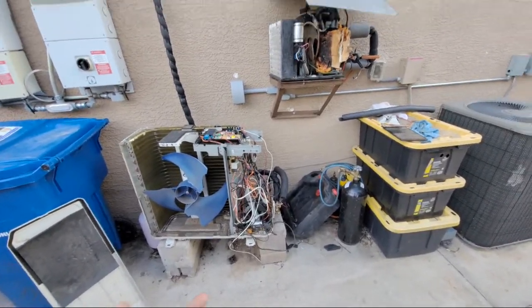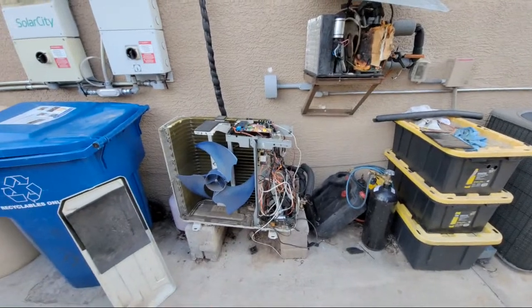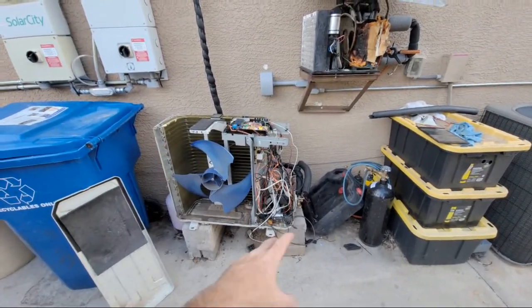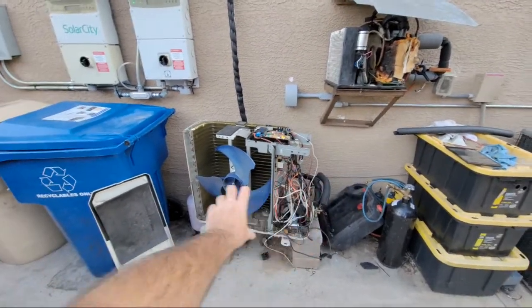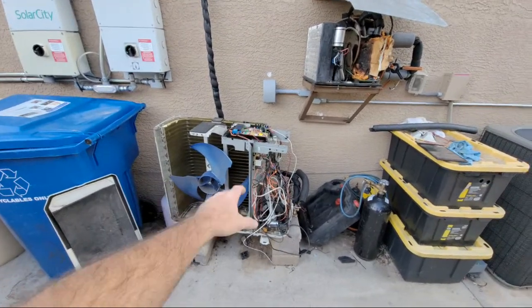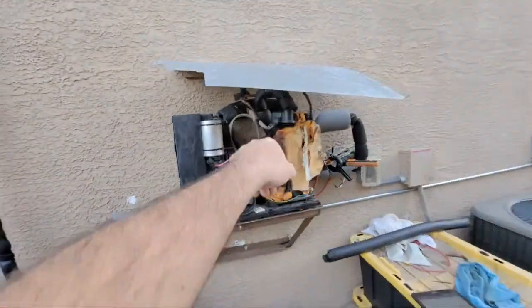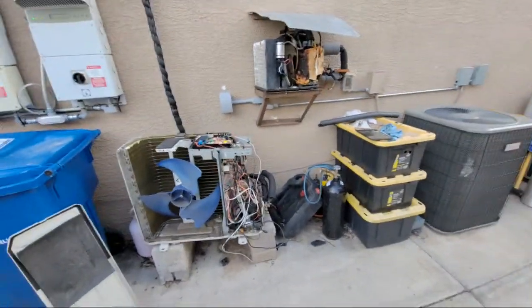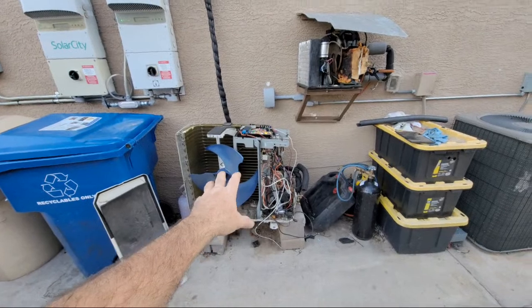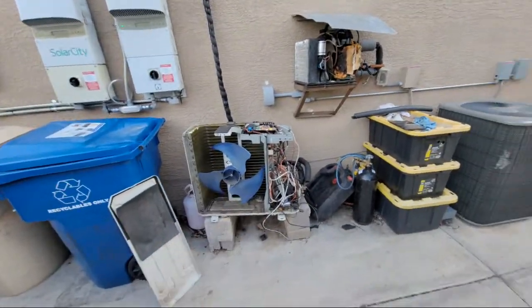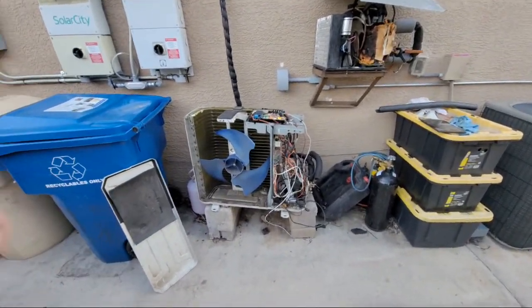And it's just funny because it's just the same compressor, put down in there, and because I added a direct air heat exchanger after the water heat exchanger, thinking that's going to bring the head pressure down a little bit, be more efficient, especially when running it in AC only in the summer with the pump off. It has to have that coil. It was just in my mind that it should work, but it didn't.